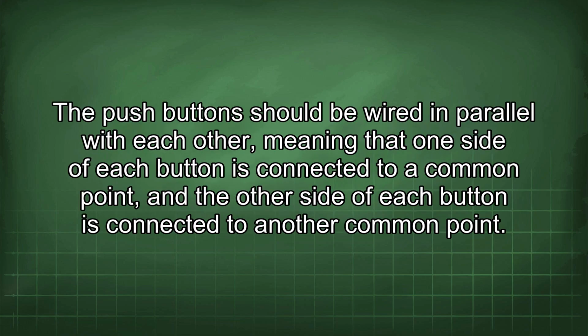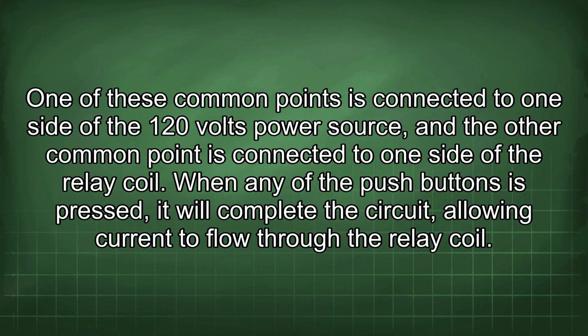The push buttons should be wired in parallel with each other, meaning that one side of each button is connected to a common point, and the other side of each button is connected to another common point. One of these common points is connected to one side of the 120 volts power source, and the other common point is connected to one side of the relay coil.